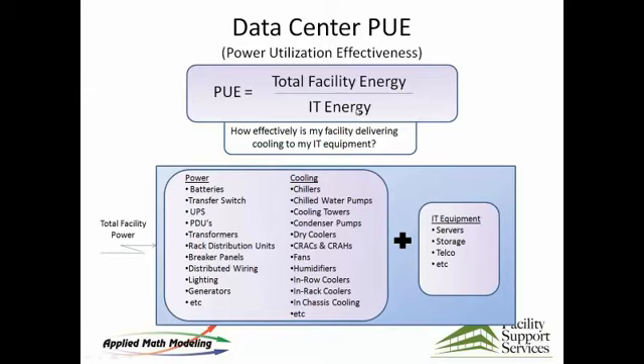And in some cases, I noticed right over here, we've got one pointing in one direction, one pointing in the other, and so we're going to have air going right around in a circle there. Yep. And you've also got a couple cases where you're blowing air from front to back into an area where there's perforated tiles in the floor. So, yeah. So we've got some classroom style configurations, which I've run into a couple of different times. That's an older configuration, and you see it over here on the right.